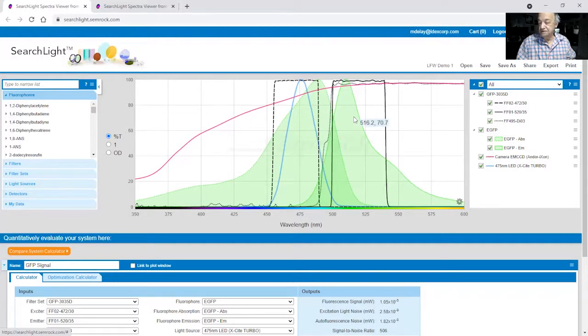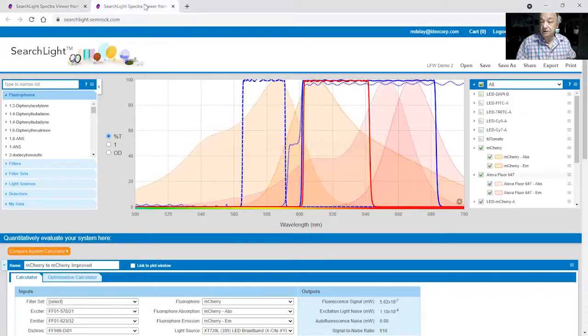But if you want to look at something quantitative in order to optimize something, then you can use it in that mode. And here's another example with a little different situation. Here we have an M-Cherry filter set here. So that's the excitation, the dichroic in dotted line, and the emission filter, quite wide. And the spectra of two fluorophores, M-Cherry on this side and Alexa 647 on that side.